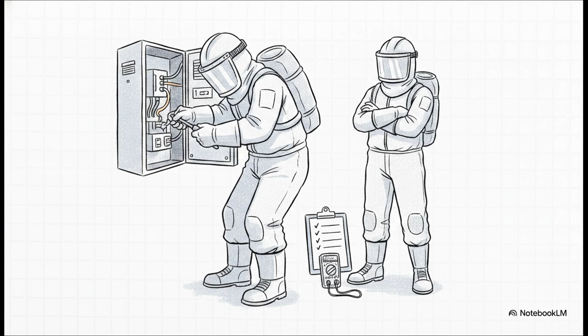But what if you absolutely have to work on live equipment, like when you're testing for polarity? Well, working on energized equipment is only permitted under very strict specific circumstances. You need a competent person, properly tested tools, a formal safe work method statement, and usually a safety observer. These protocols are non-negotiable, folks.